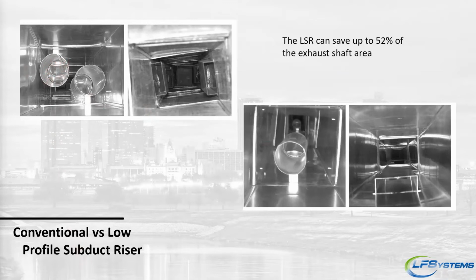And so what we introduced several years ago now, what we call our low profile subduct. It's actually a round to rectangle transition piece. So this would be a 4-inch inlet, and then it just makes it into a 2.5 by 7-inch rectangle. Gives the same open free area as the 4-inch pipe, but now it's a much cleaner, much smoother transition in the duct, and it provides a lot more open space in the middle of that shaft. So we can actually save up to 52% of free area in your shaft using the low profile subducts versus a field fabricated subduct.